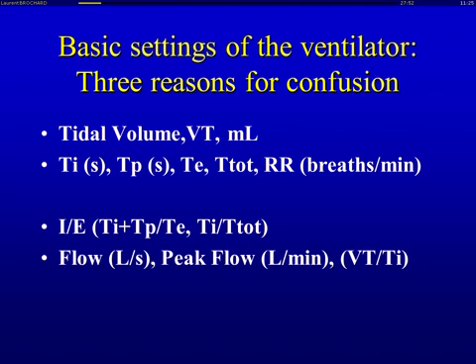A first source of confusion when you have different ventilators in your unit is that for volume control ventilation, you have two ways of setting flow. One way is to tell the ventilator about timing — for instance, the classical I:E ratio. Many ventilators work with the I:E ratio by default: the ventilator knows the total breathing time, you tell it the I:E ratio, it calculates the inspiratory time, and from the volume and inspiratory time it knows which flow to deliver. On other ventilators, you directly dial the flow.